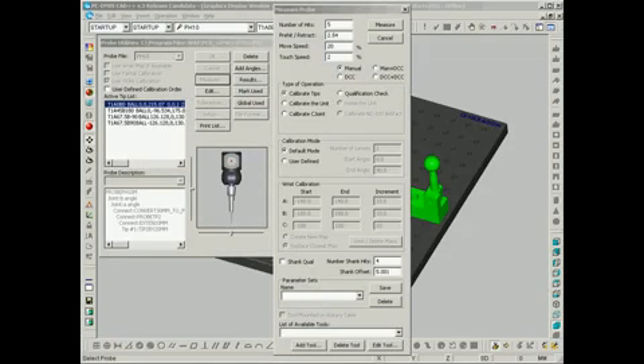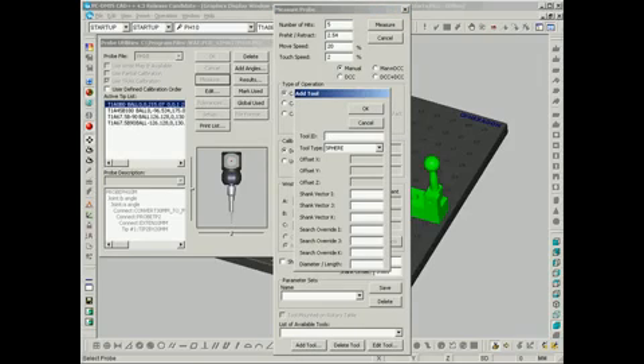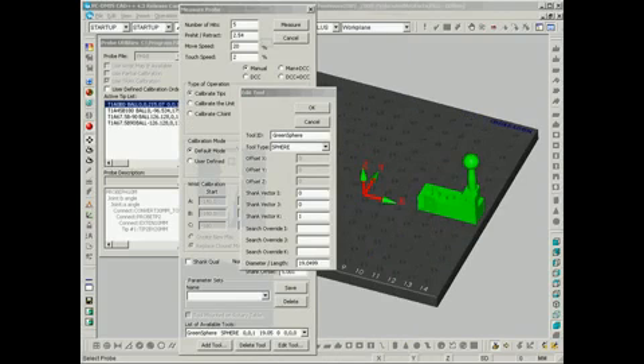The next thing we need to do is add a hardware profile that describes this tooling ball. So under Measure Probe, we're going to select Add Tool, and we're just going to build up the profile for each of these calibration tools. It's important that you get the calibration artifact's vector correctly inside of the Edit Tool dialog. You'll notice this green sphere points in the Z+ direction, and so I've input a vector of 0, 0, and 1, and then down here I've added its size.